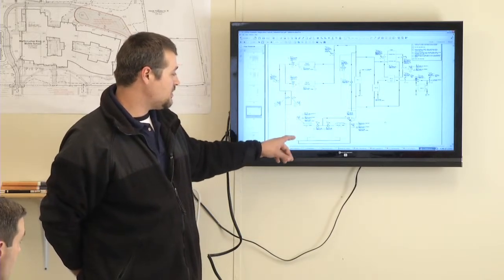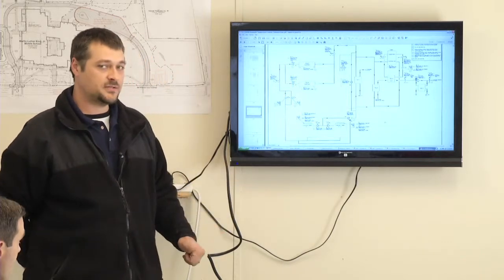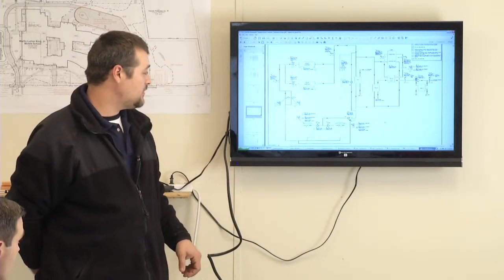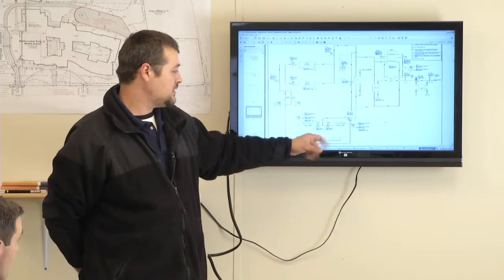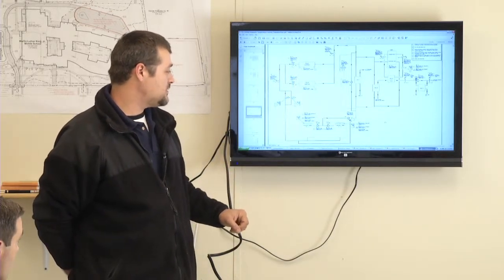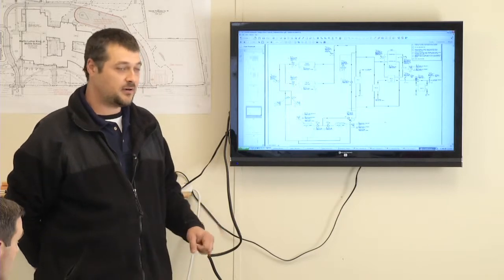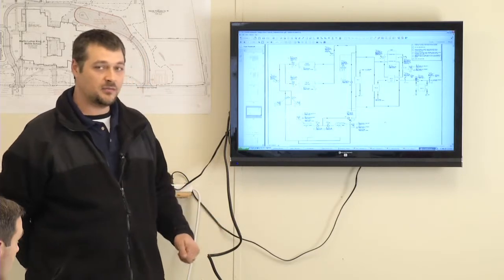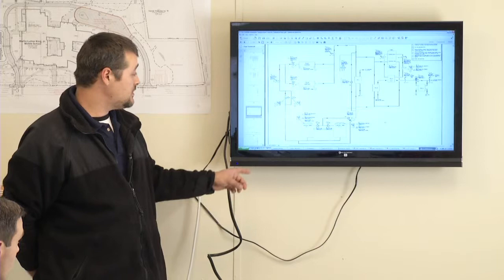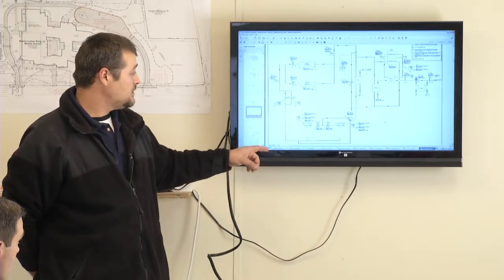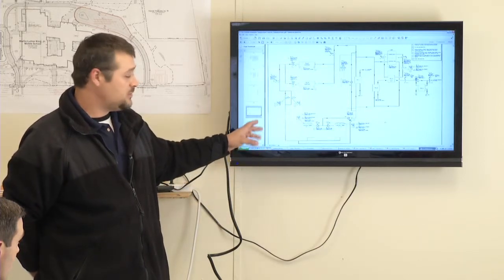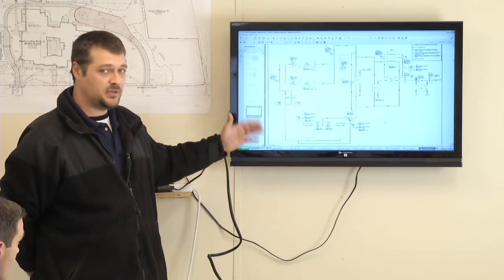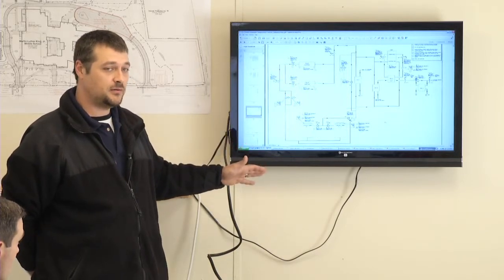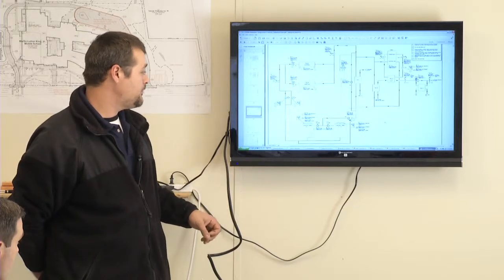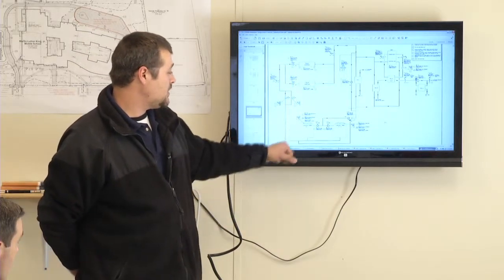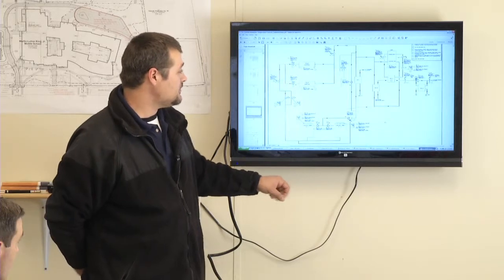They control the cooling tower fans. We control both the start-stop and the speed of each drive. And then we'll have proofs inside of the drives to pick up current off the motors. We have BACnet communication to all these pumps and fan drives, and the pumps on the skid are completely controlled through BACnet. There's no hardwired control of those whatsoever. But we do have hardwired controls on the cooling tower fans.